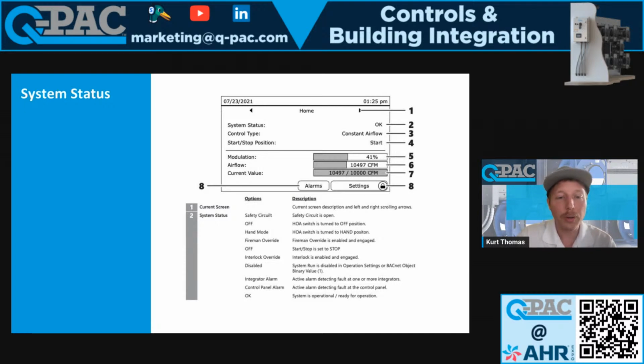It's super simple. It only shows one at a time, in descending order, right? So if your safety circuit's tripped, that's going to be the highest priority. And if multiple things are tripped, only the highest priority one's going to show. But yeah, it's super easy to diagnose our system whenever you have that. So if you're doing startup and you don't understand why it's not running, more than likely your answer is going to be looking at this system status.